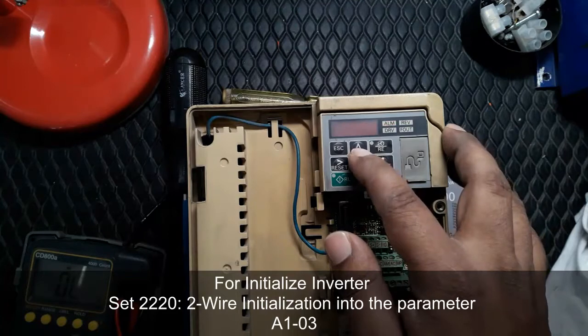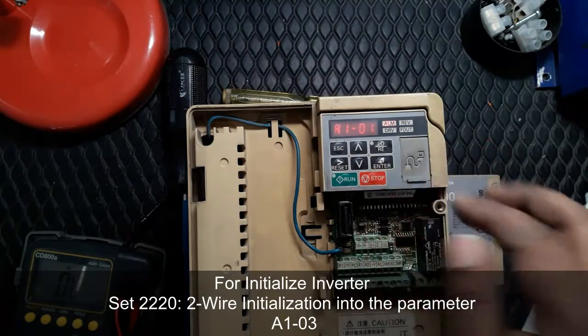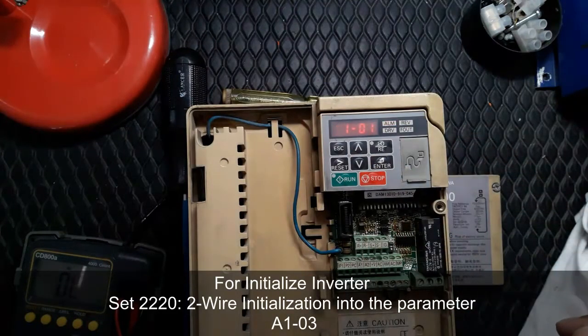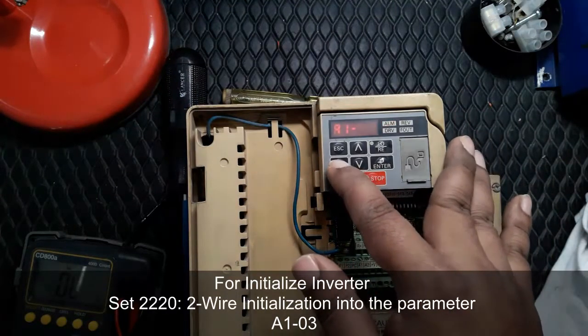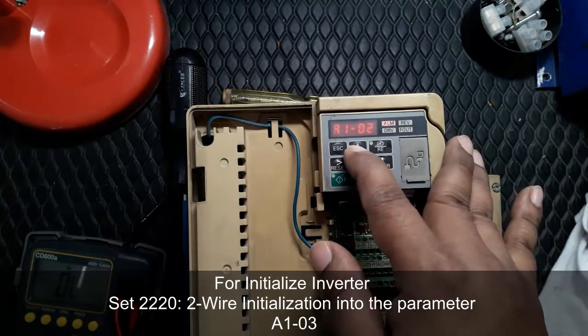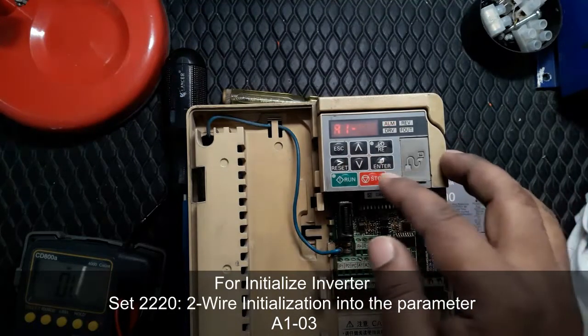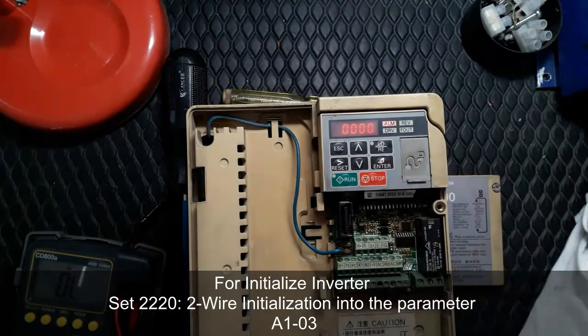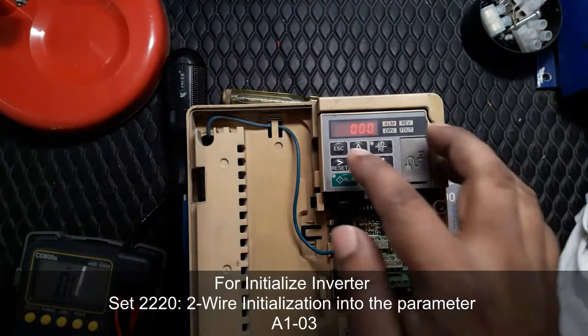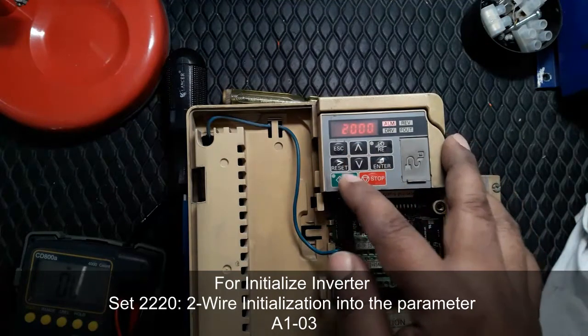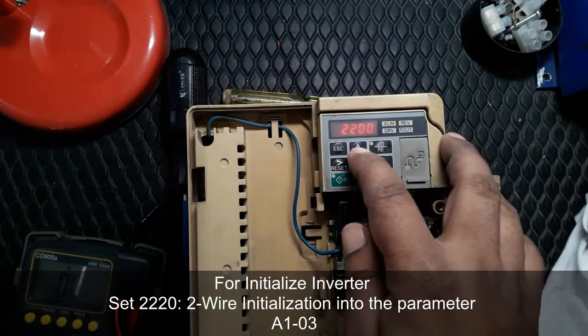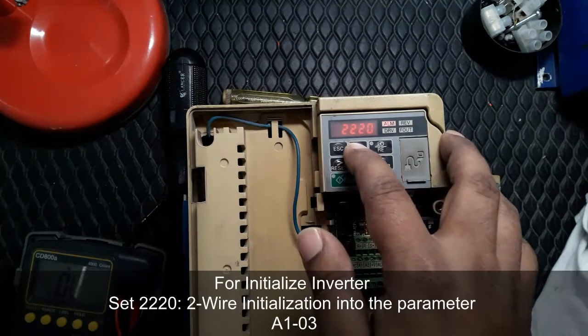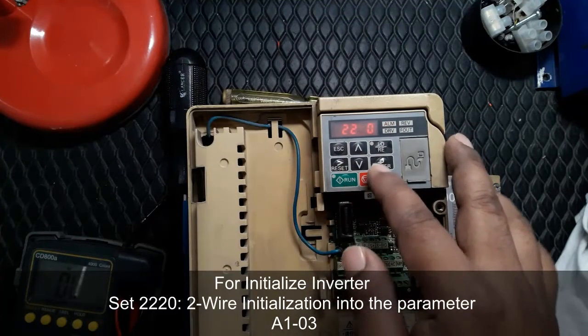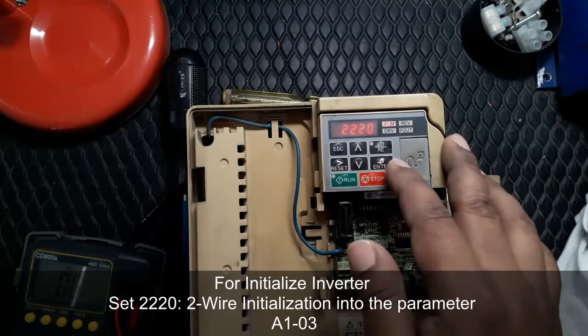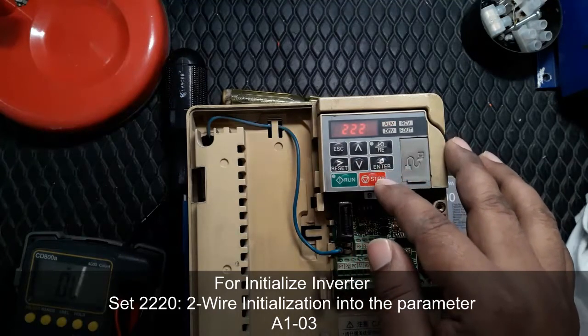So for initialization we need to enter into the parameter A103. Here A101, press reset 2 times and up button 2 times, now A103 and enter. Set here 2220 for 2-wire initialization. By reset and up button we set 2220 and press enter for initialization.